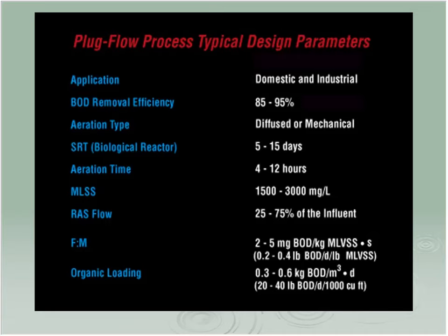If you're not paying attention and something's starting to happen to your process and your volatile number is starting to go down, if you're just looking at mixed liquor solids, you may never see that until somebody comes back with a BOD number that says 28, when it's supposed to be 15. Oops. So it helps to watch what's going on. You want to make sure that this ratio at a constant level tells you you've got a good, healthy population that runs in your facility. So it should be looked at.